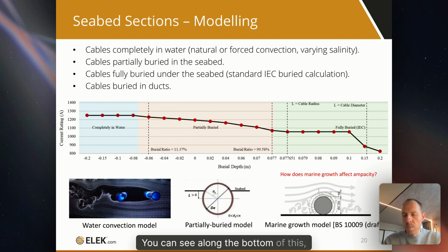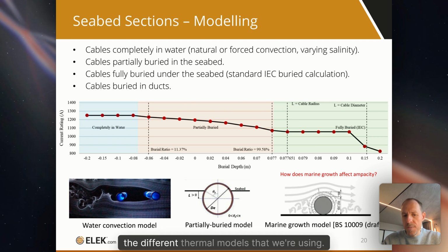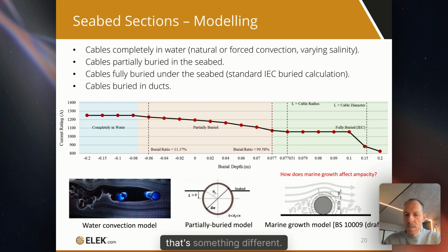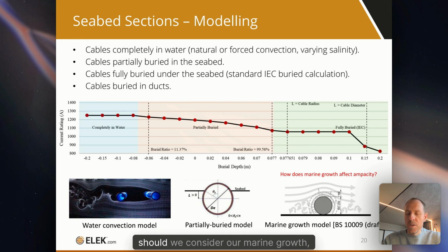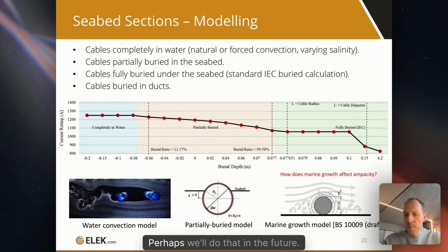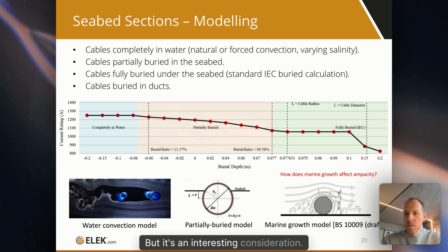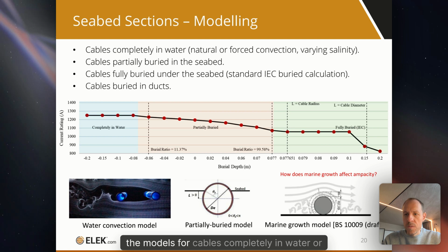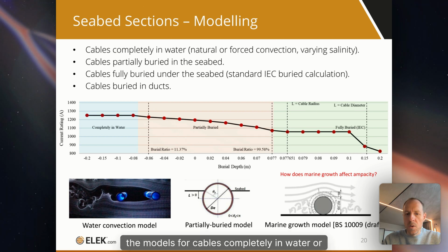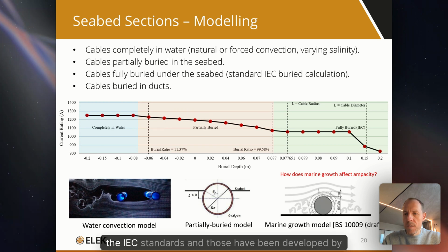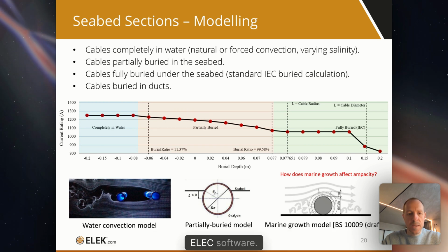You can see along the bottom of the slide here the different thermal models that we're using. Not the one on the bottom right-hand corner, that's something different. That's where I'm making a point that should we consider marine growth for ampacity calculations, perhaps we'll do that in the future, but it's an interesting consideration. Now, it should be pointed out that the models for cables completely in water or partially buried are not available within the IEC standards, and those have been developed by ELEK software.